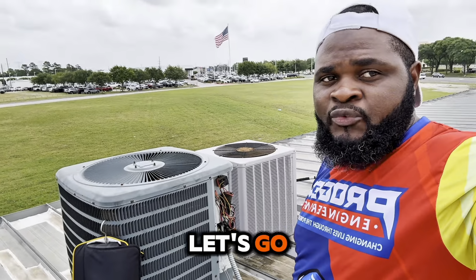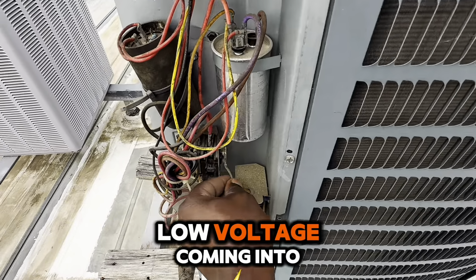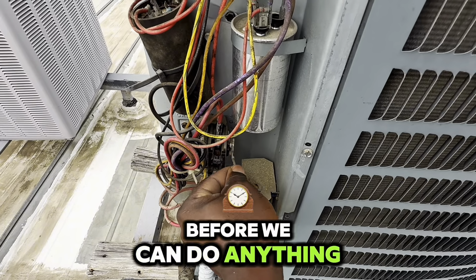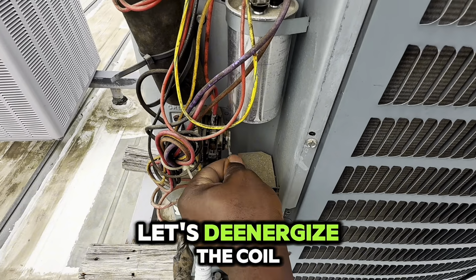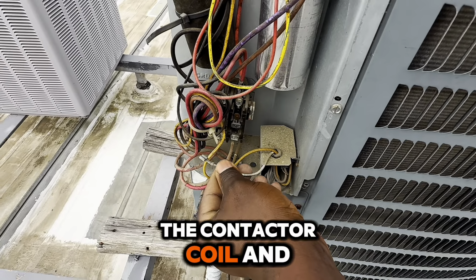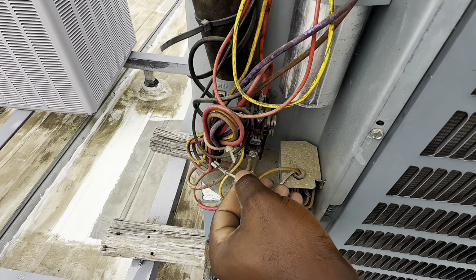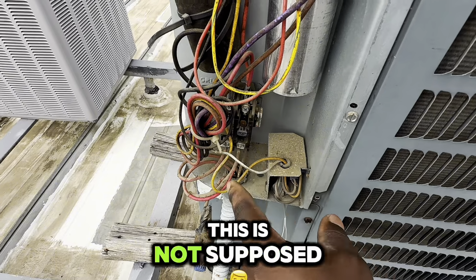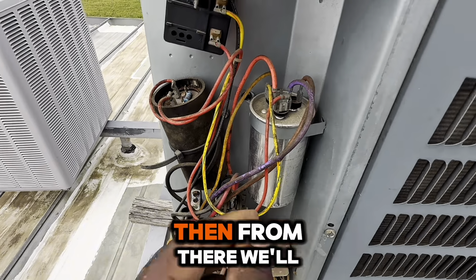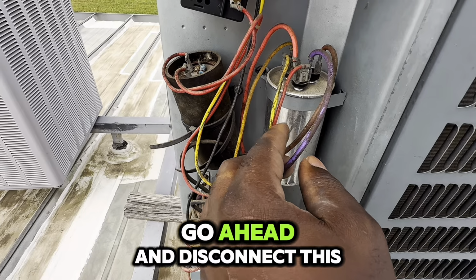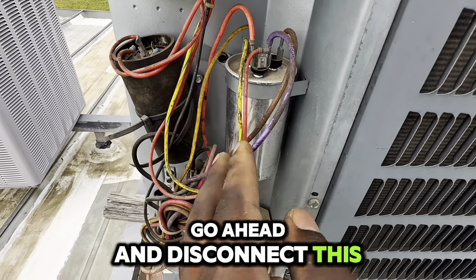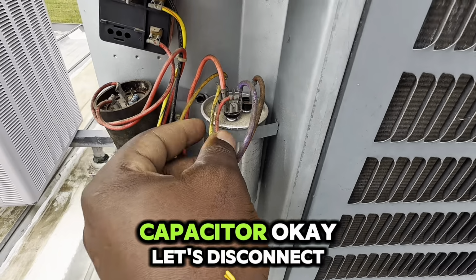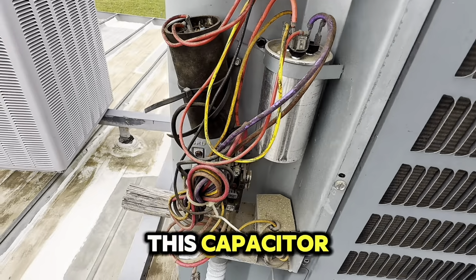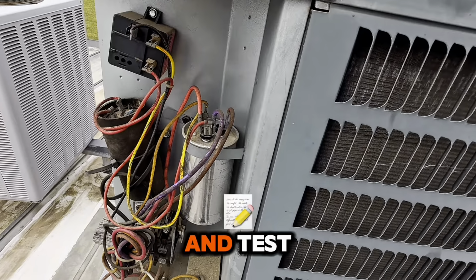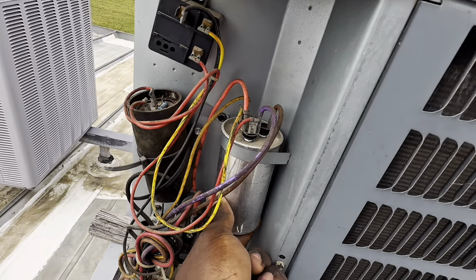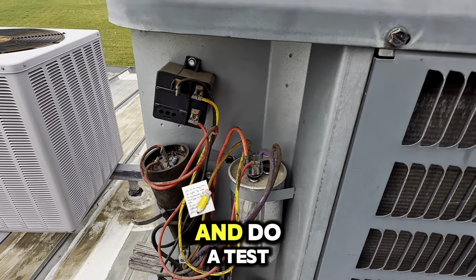Okay, let's go. I'm going to kill the low voltage coming into this unit. Before we can do anything, let's pull this out. Let's de-energize the coil, the contactor coil, and be careful. This is not supposed to have any contact anywhere. Then from there, we'll go ahead and disconnect this capacitor. Okay, let's disconnect this capacitor and do a test.